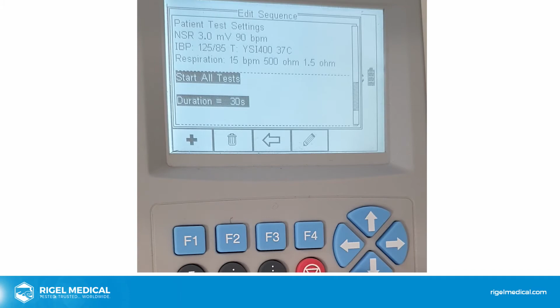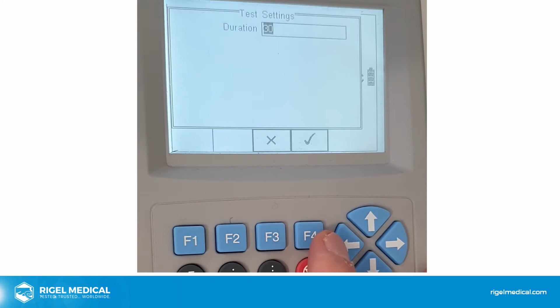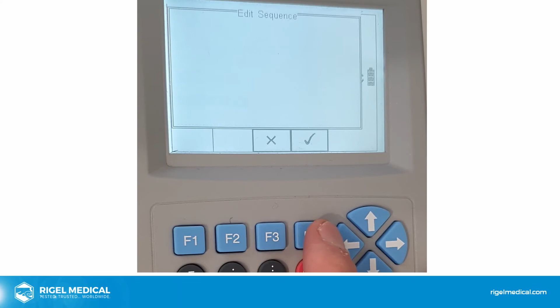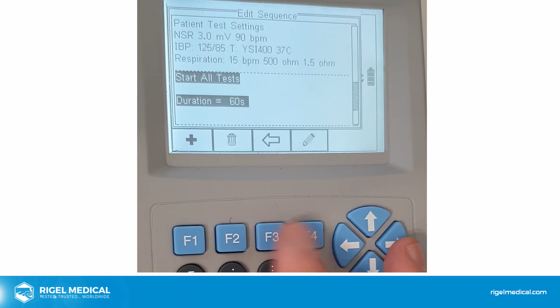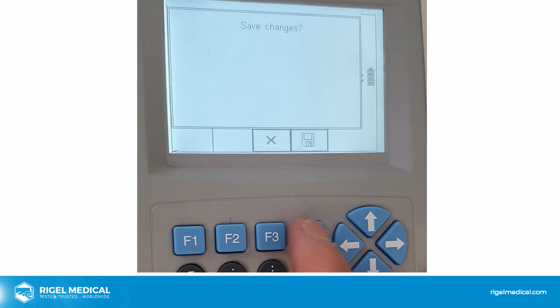And we'll leave the other values as they are. Now, with the setup, it sometimes takes a while for the measurement on the monitor to stabilize. So the standard duration is 30 seconds, but I prefer to set it to 60. Enough time to get stabilized values. So now this test sequence is set up for this particular monitor.